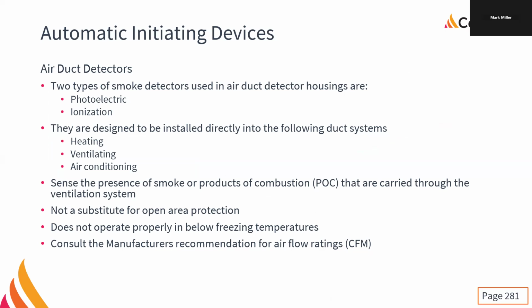We can use photoelectric or ionization. 99.9 times out of 100, it's going to be photoelectric. And we put them in the heating, ventilation, and air conditioning duct systems. They are not a replacement for open area protection. Our smoke detectors out in the patient rooms and hallways and all that still have to go in. It's only to detect smoke inside the ductwork.